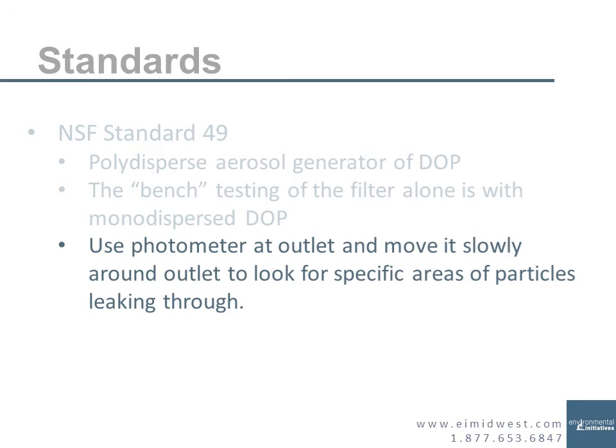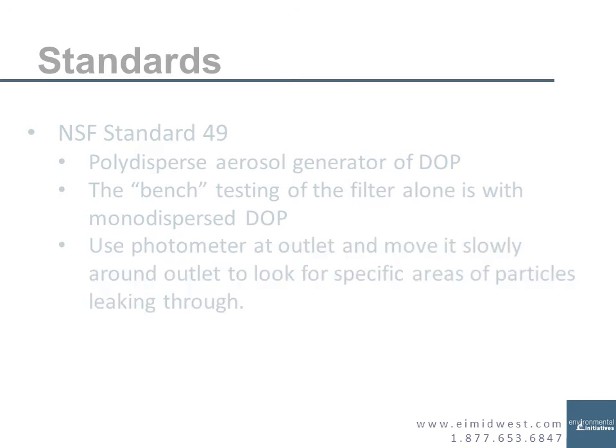You go across the face of the filter and you can find leaks and go, okay, well this is where the filter is leaking, and it's leaking in the side, it's leaking in the corner. We need to replace these parts or replace the filter in general.